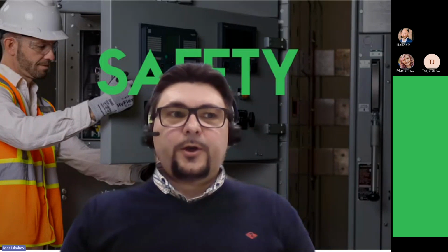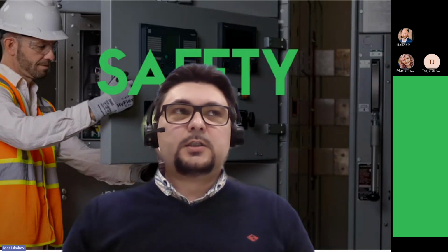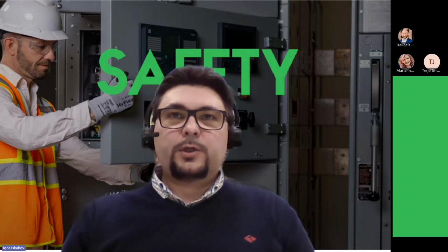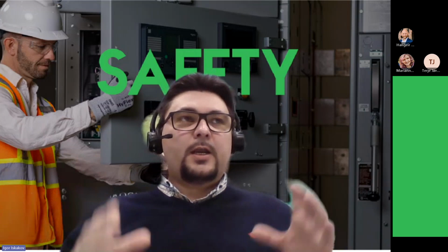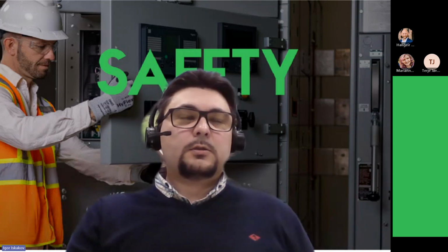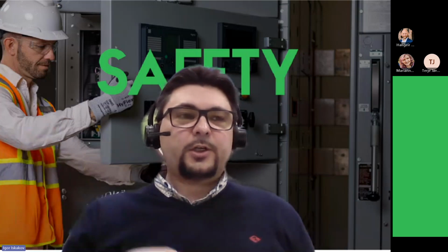False trip. Yeah, Trond, you are exactly correct. A3 is mainly a light only system, so if you have sparking and the like, this system will be activated. You're correct. For securing against this false tripping from sparking or, like, a person's flashlight, for example in switchgear parts, we recommend using our 3-to-1 system, which has current and light. The current condition eliminates false tripping from sparks or flashing lights.